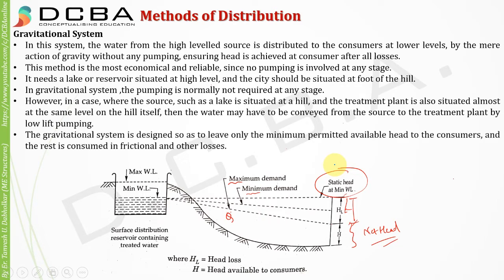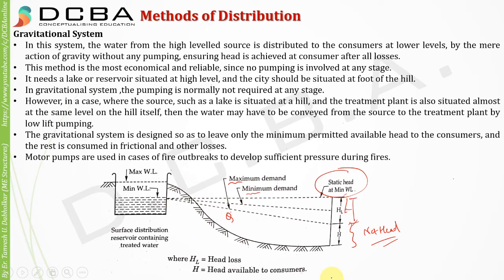The gravitation system is designed so as to leave only the minimum permitted available head to the consumers, and the rest is consumed in friction and other losses. Motor pumps are used only in case of fire outbreaks to develop sufficient pressure during fire, because during fire we need higher discharge and higher pressure. If the gravitational system is not able to develop sufficient pressure head during fire, some motor pumps may be used to help pump out the water.